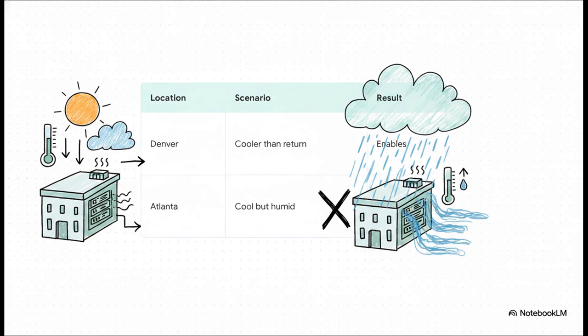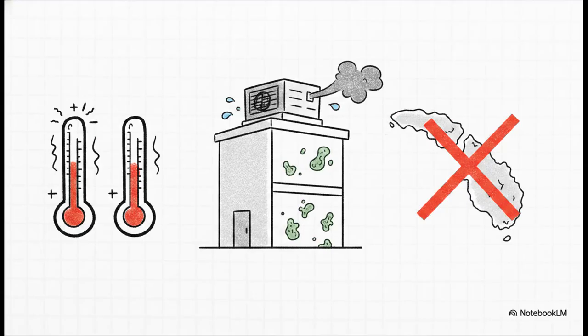This is honestly brilliant for a building with unpredictable internal heat loads, like a big data center in dry Denver. If those servers are running hot and the return air hits 75, but it drops to 70 outside, the system happily sucks in that cool air. But take this to humid Atlanta, and relying strictly on temperature comparisons can be a total disaster. The outdoor air might technically be cooler than the indoor air, but if it's loaded with moisture, it's going to crank your indoor relative humidity to damaging levels above 60%. Plus, because you're using two sensors now, you're actually compounding their potential for error, amplifying that inaccuracy to plus or minus 4 degrees.